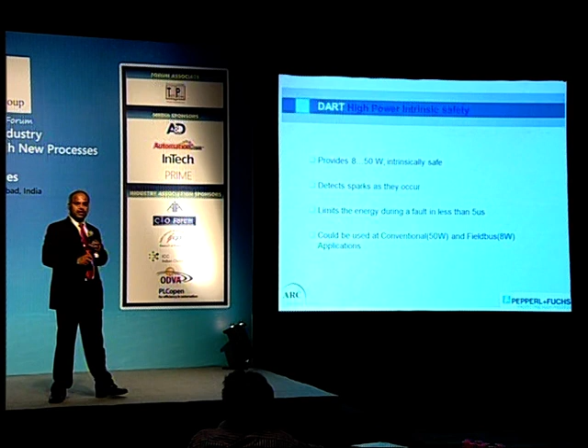By using this technology we can bring up to 50 watts and still be intrinsically safe. For a typical fieldbus we don't need more than 8 watts. In a conventional traditional ExD equipment with unlimited energy, such as high-powered DC, this brings a lot of other restrictions.